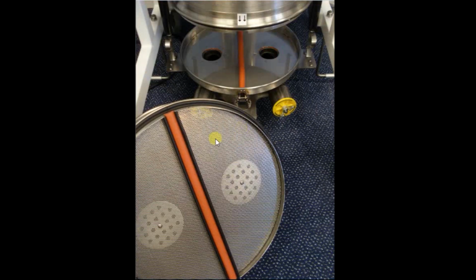So this seal marries with this seal on the bottom of the soda lime tray, and that's why this tray has to be put in only one or two ways, but this main seal on the bottom must line up with the main seal on the absorber pan, and in this way gas cannot pass from one side to the other.